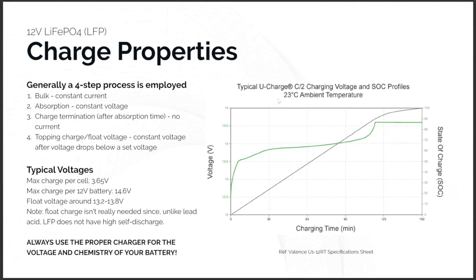So when it comes to charging, there's essentially for lithium ion - I've listed a 4-step process here, but it boils down to 2 steps: a constant current and then a constant voltage. Usually, as you can see from the chart here, it's a C/2 charge current, so if this is a 40 amp hour battery, you're charging it at 20 amps. Once it's reached a certain cell voltage, in this case usually between 14.4 to 14.6, really max 14.6, then you're switching to a constant voltage.